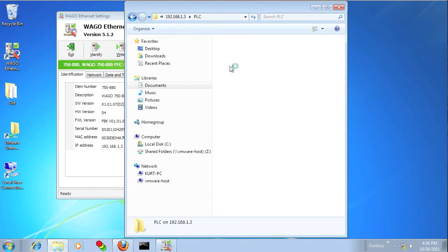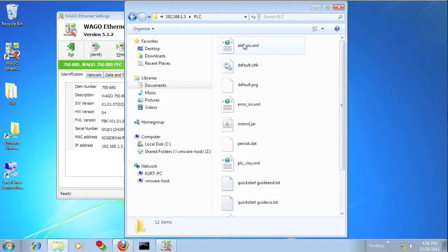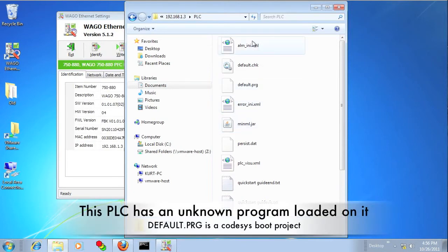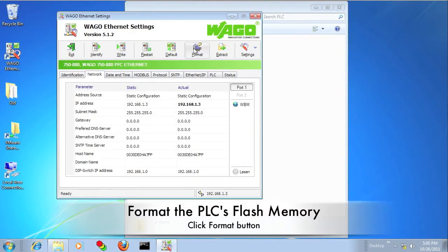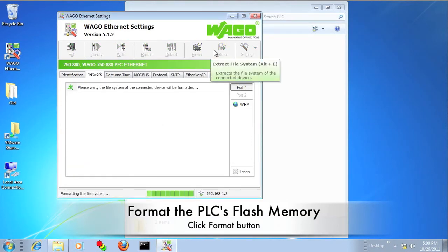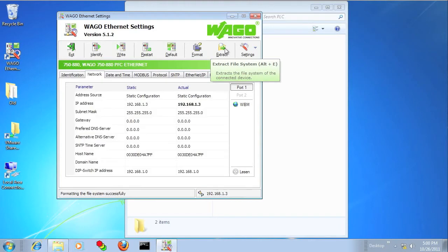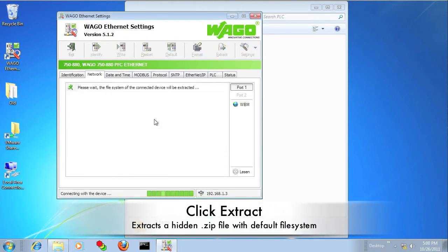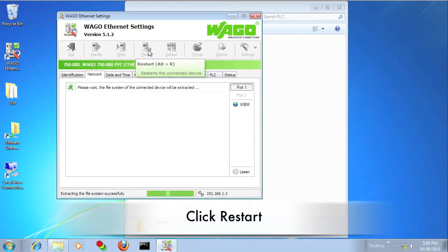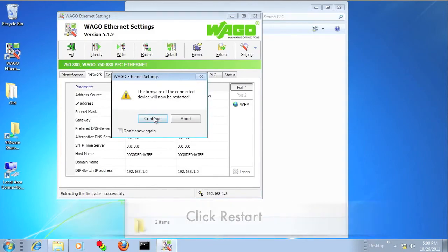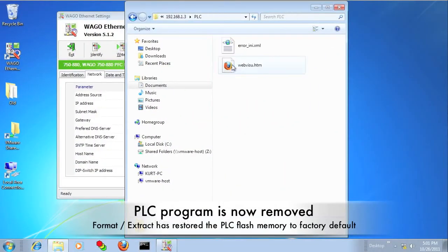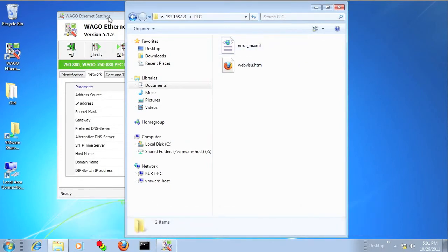In this example I've got an unknown program loaded on the PLC, and I'm going to show you how to clear out the flash memory using Ethernet settings. Click the Format button to format the flash to the FAT file system. Then click Extract — there is a hidden zip file that will uncompress a default configuration back onto the flash memory. Then click Restart. Going back into the FTP client, you can see it is back to the original default state.